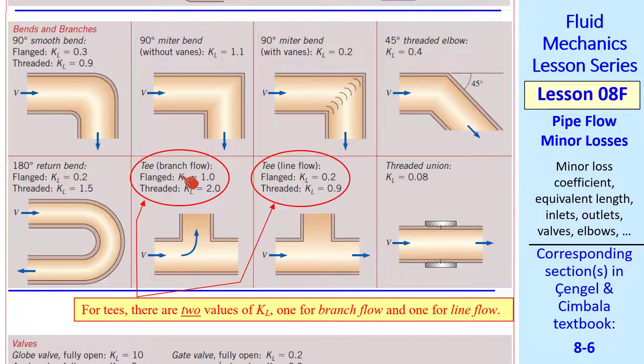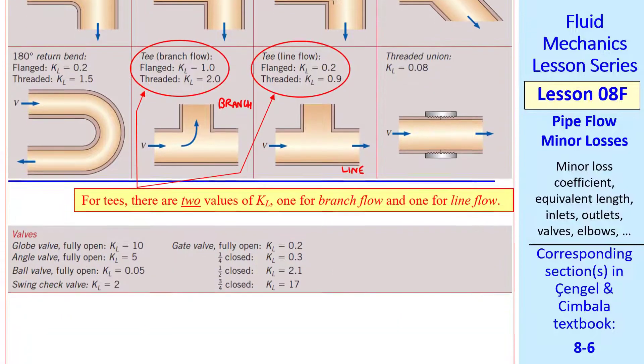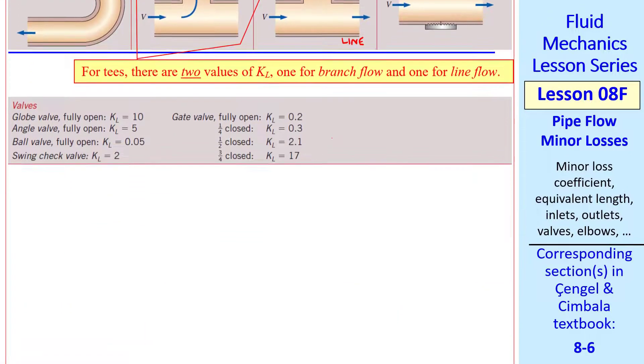Note that for Ts, there are two values of KL. One for the branch flow and one for the line flow, where the part coming off is the branch, and the part continuing straight on is the line. There are also KLs listed for various kinds of valves.